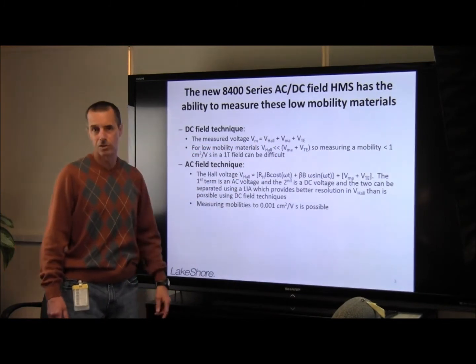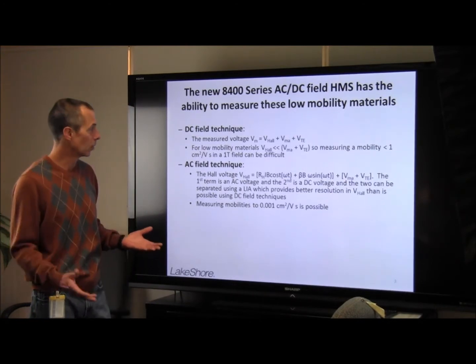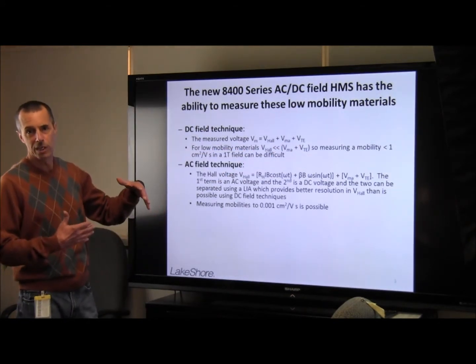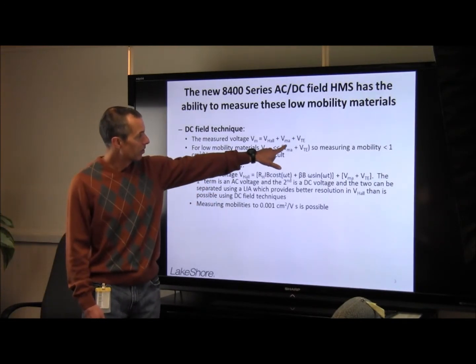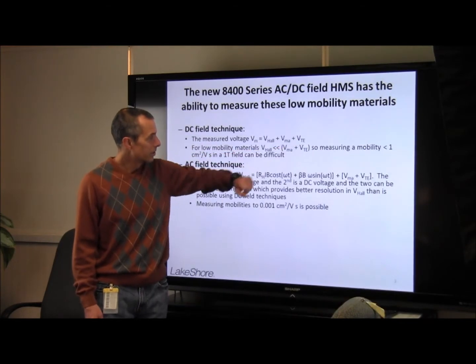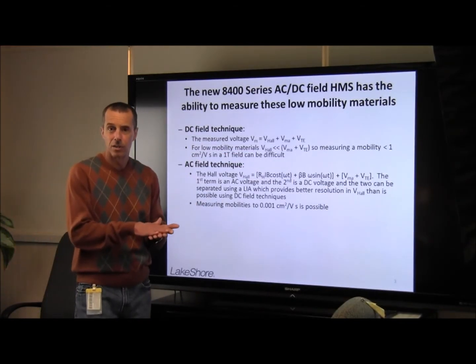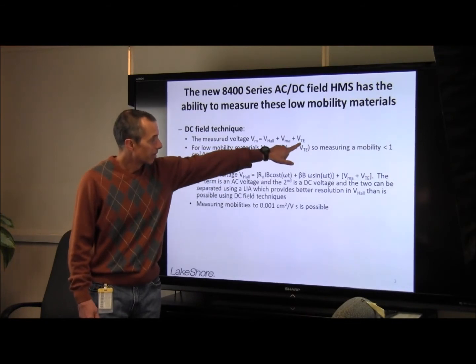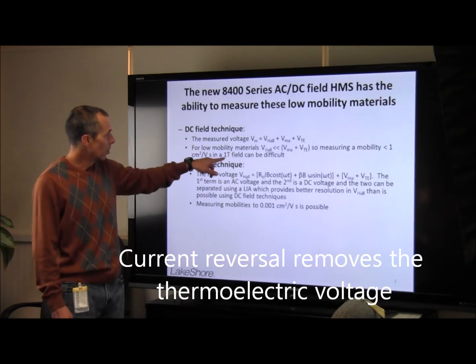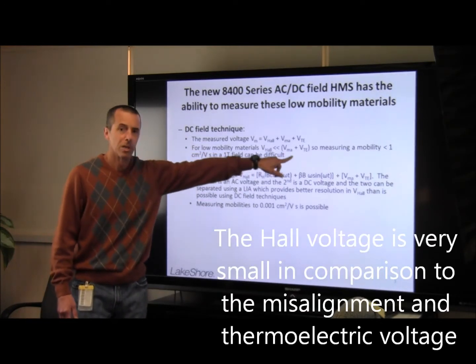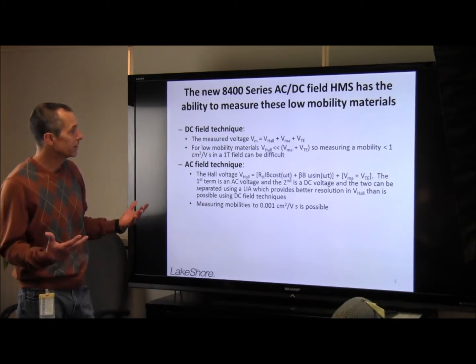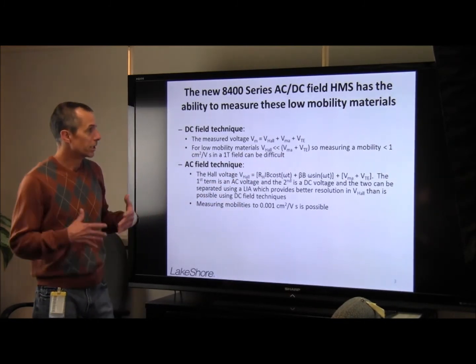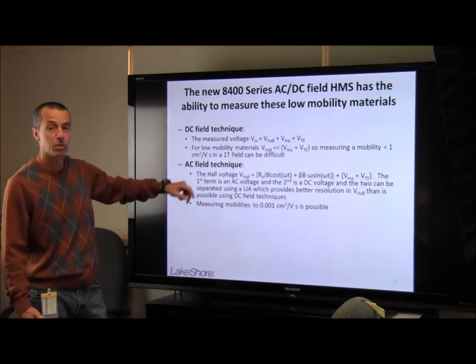The principal contributions to the offset voltage are a misalignment voltage and a thermoelectric voltage. The misalignment voltage is due to misalignment in the point contacts on the sample, and this can be removed by using field reversal. The thermoelectric voltage is due to the fact that you have metallic contacts on top of a semiconductor, and these dissimilar materials give rise to a thermoelectric voltage, which can be removed using current reversal. However, for very low mobility materials, the Hall voltage is considerably small in comparison to these offset voltages, making it very difficult to extract. Consequently, it is very difficult to measure mobilities less than about 1 centimeter squared per volt-second.